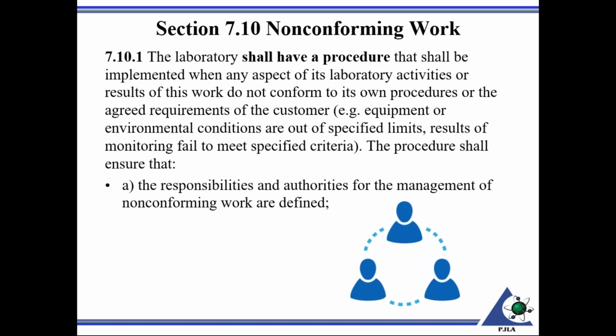Or perhaps you do have checks on your balances where, prior to doing a calibration or a test on this particular balance, you have test weights that you use. You have data on those test weights, and you have predefined limits of acceptance. An example there would be exceeding those predefined limits, and however, still producing reports to the customer despite the equipment being out of those predefined limits.